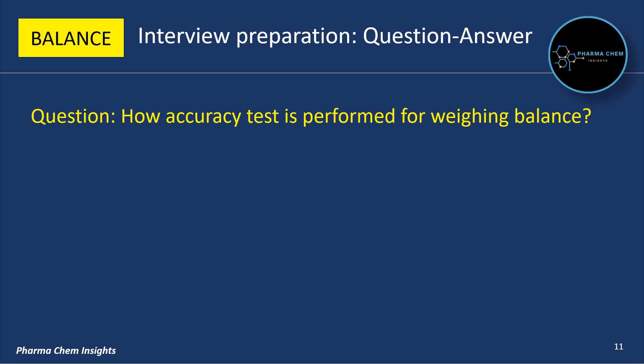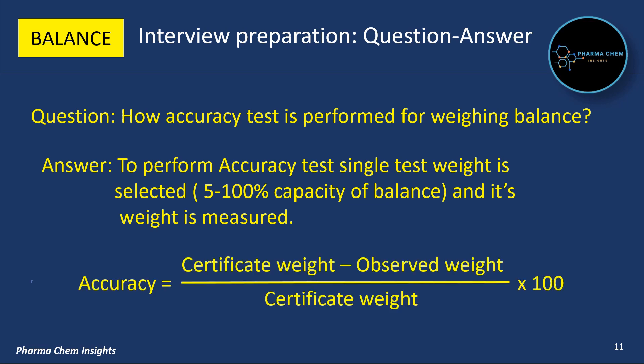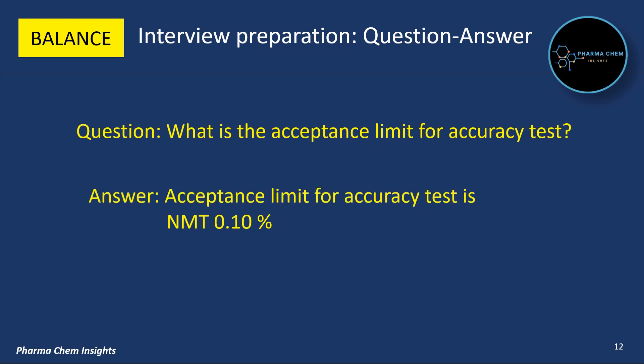Next question: how is the accuracy test performed for a weighing balance? To perform the accuracy test, a single test weight is selected between 5 to 100% of the balance capacity and its weight is measured. The formula to calculate accuracy is: Accuracy = ((Certificate Weight − Observed Weight) / Certificate Weight) × 100. The acceptance limit for the accuracy test is not more than 0.10%.